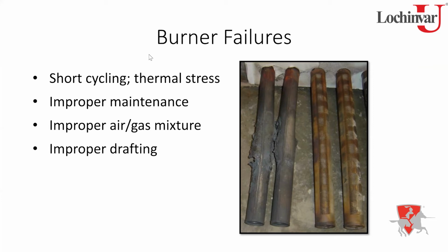Also, if you start to pull burners out and you see multiple are cracked in the same location, that's a good sign you may be condensing, and that condensation is constantly dripping on that portion of the burner, causing it to crack. So again, we talked about how the bypass works. That would be one of the first places I would go back and look at.